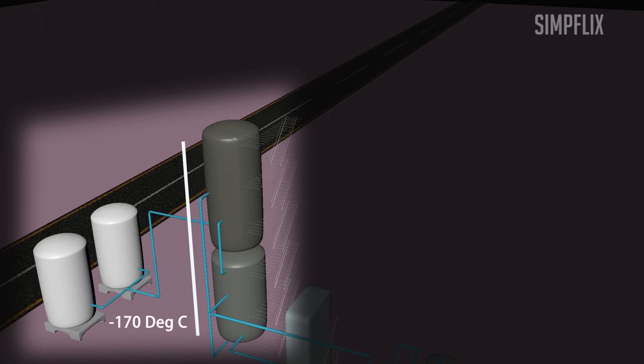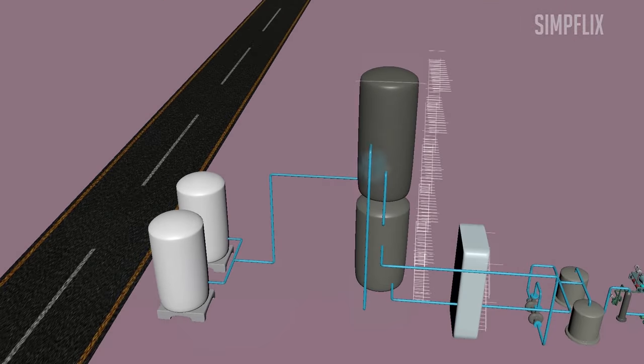By repeating this process for long time, there will be a formation of temperature gradient from bottom of the distillation column to the top. From minus 170 degrees Celsius at bottom of the column to minus 196 degrees Celsius at the top of the distillation column.